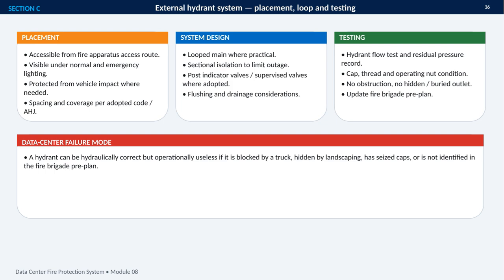From a system design perspective, a looped main is preferred where practical because it can improve resilience. Sectional isolation helps limit the area affected by an outage, while post-indicator or supervised valves may be required by the adopted criteria. Flushing and drainage also need to be considered, not treated as afterthoughts. Testing should document hydrant flow and residual pressure, while also checking the cap, threads, and operating nut. Confirm that outlets are not obstructed, hidden, or buried, and update the fire brigade pre-plan.